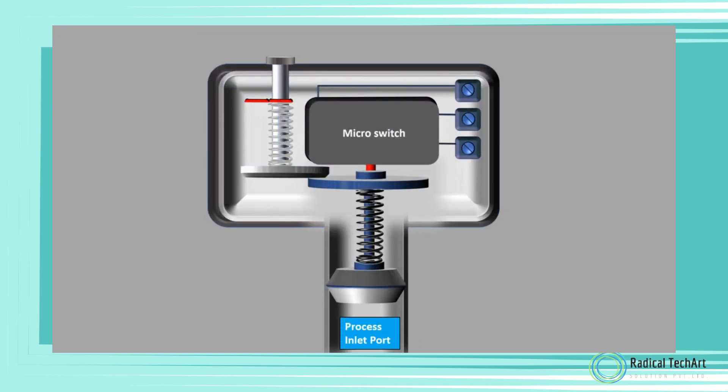Parts of a mechanical pressure switch: Process inlet port - the inlet port is the part that connects the pressure switch into the process unit. Pressure sensing element - this is the main part of the mechanical pressure switch which mechanically deforms according to the fluid pressure and actuates the switch. Diaphragm, piston, or bourdon tube is usually used as pressure sensing element.